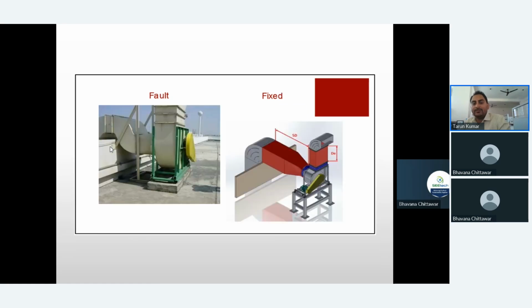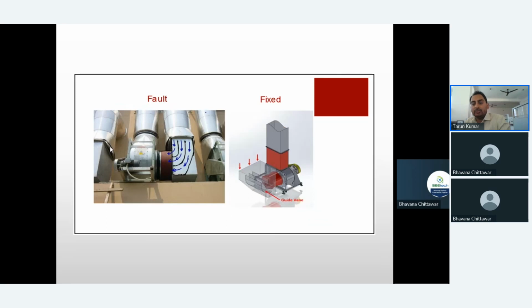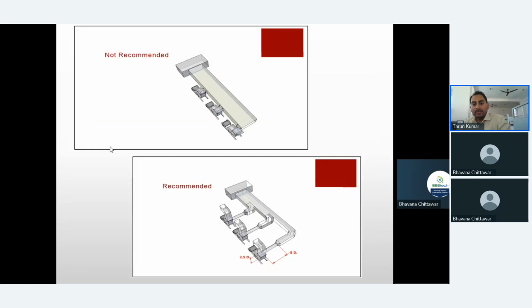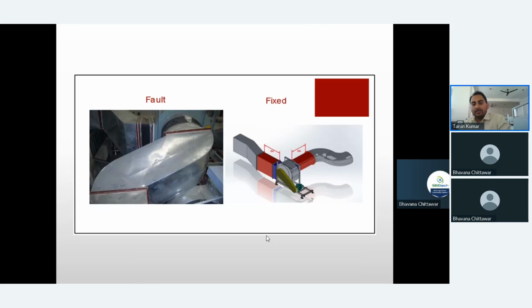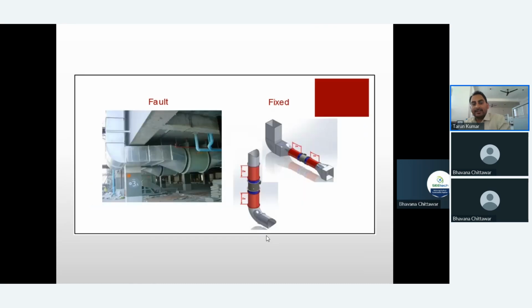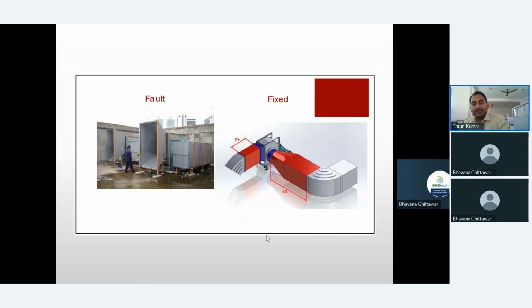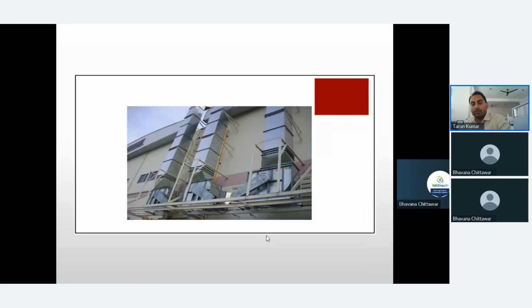The main purpose of showing all these installations was that if you select the right fan with the right orientation, you can avoid the pressure loss, and your fan will become more efficient with lesser power consumption. Then again, see the branching kind of arrangement: in a single plenum it is not recommended. You have to give different branches if you are using more than two fans in a single duct plenum. So this is again a poor inlet. If you have such an arrangement, try to avoid it. Go for the straight duct to make your system more efficient.